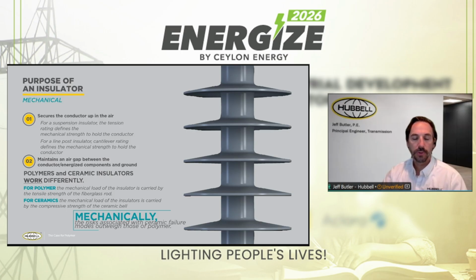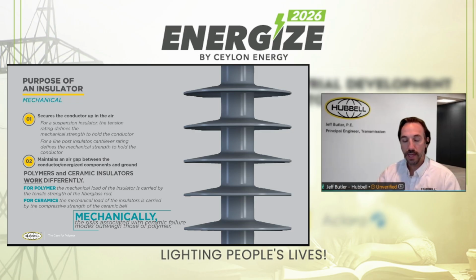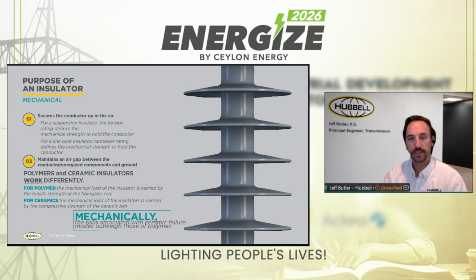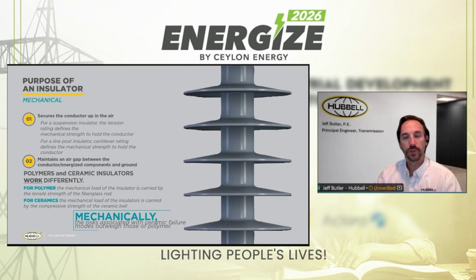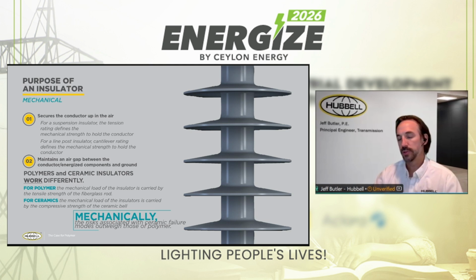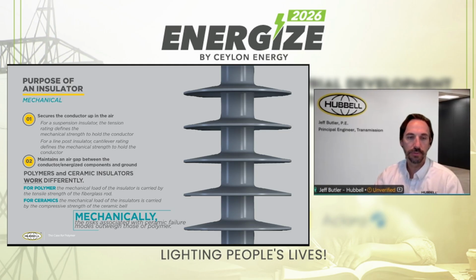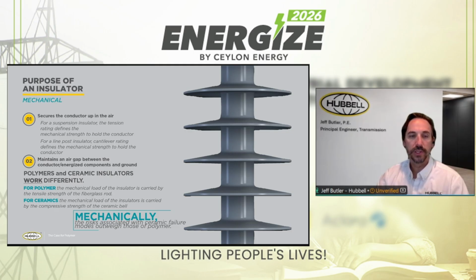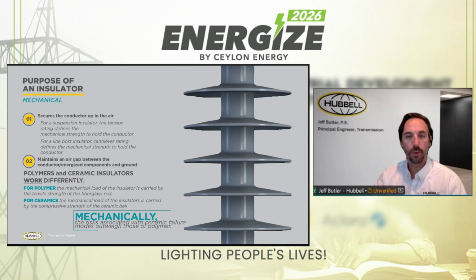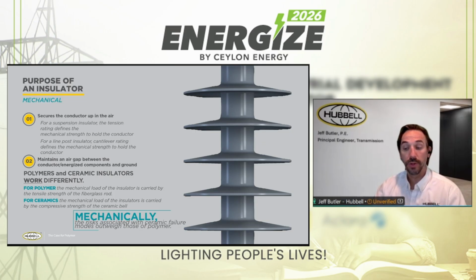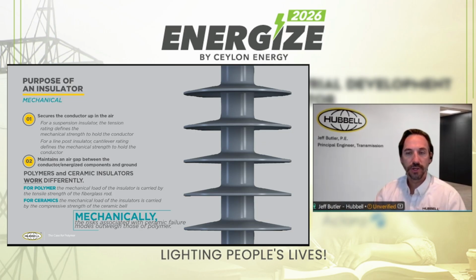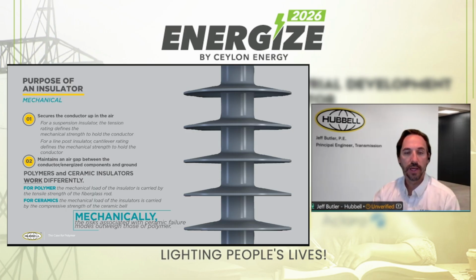little bit different. So for a polymer insulator, the mechanical strength of the insulator is the fiberglass rod. So the most important part of the insulator is the fiberglass rod. It needs to be protected. It needs to maintain its strength, maintain its integrity, and then it is crimped to metal end fittings, which then help to transfer the strength of the fiberglass rod to the structure, to the tower, to the conductor, to the other parts and pieces. For a ceramic insulator, the mechanical load is carried by the compressive strength of the ceramic bell, or the porcelain or glass bell itself also serves to carry the mechanical strength as well as support the electrical function. So because of that, mechanically, there are different risks associated with the different components of a ceramic insulator or of a polymer or composite insulator.